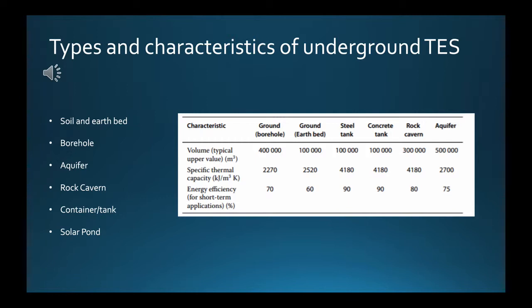Borehole TES systems are often deep, up to hundreds of meters, consisting of a network of tubes inserted into boreholes drilled into the ground. These permit heat or cold to be transferred into underground soil and rock for storage and subsequent recovery. Borehole heat exchangers are manufactured, installed, and operated in a relatively standardized manner today.